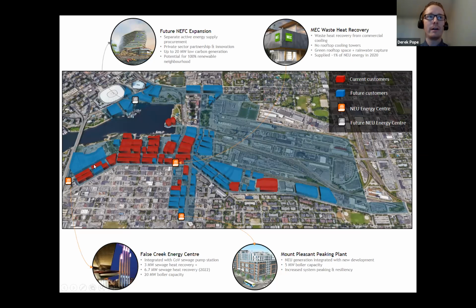Starting here, this is our False Creek Energy Center. This is where most of our energy is produced. We built a plant on top of a sewage pumping station, which gives us access to really large volumes of wastewater. So what we do is we extract some of the thermal energy from that wastewater using a heat pump. We currently have 3 megawatts of heat pump capacity for sewage heat recovery, and we're in the process of adding another 6.7. That extra 6.7 should be online by next year.